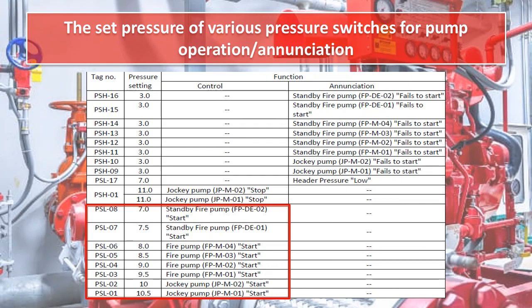From the list of pressure settings, the system is maintained at 11 kg/cm². When pressure drops to 10.5 kg/cm², the first jockey pump starts. At 10 kg/cm², the second jockey pump starts. At 9.5 kg/cm², the first main fire pump starts; at 9, the second main pump; at 8.5, the third main pump; at 8, the fourth main pump. At 7.5 kg/cm², the first diesel engine starts, and at 7 kg/cm², the second diesel engine starts.